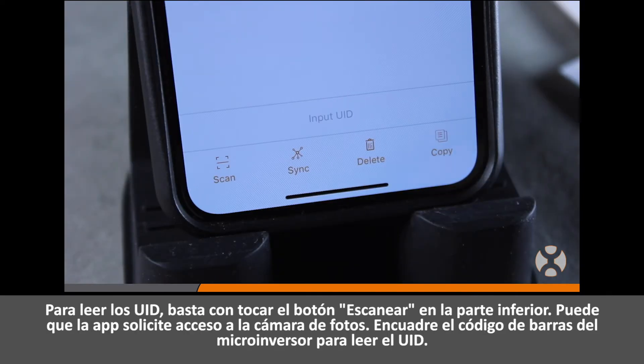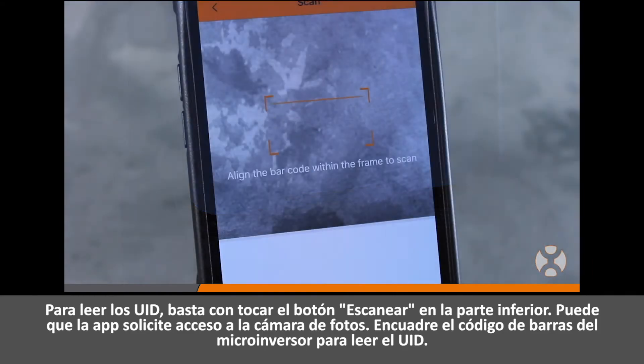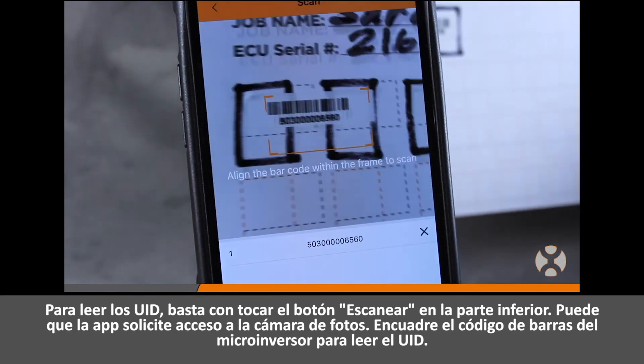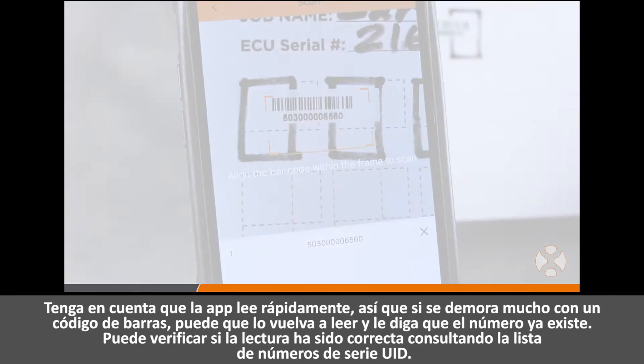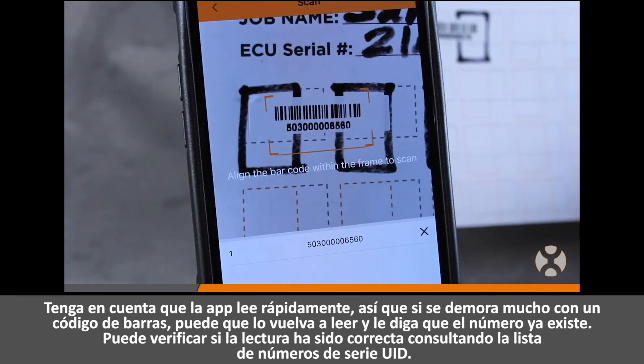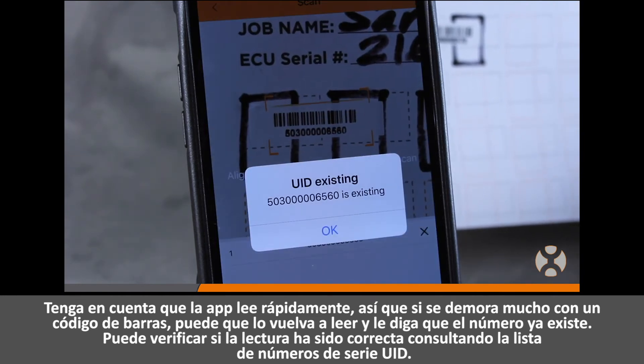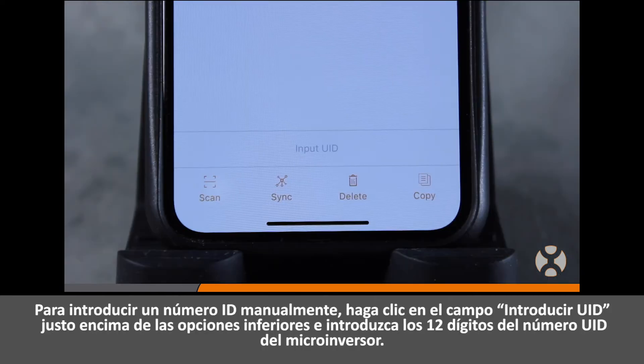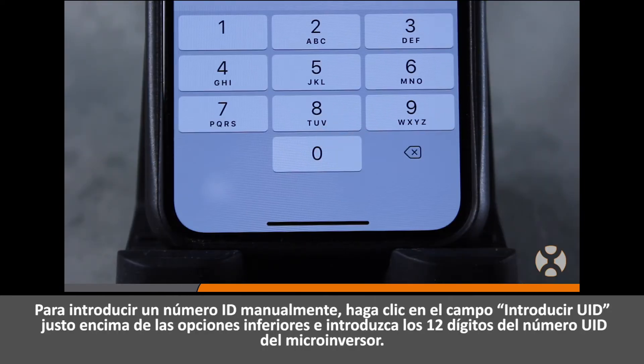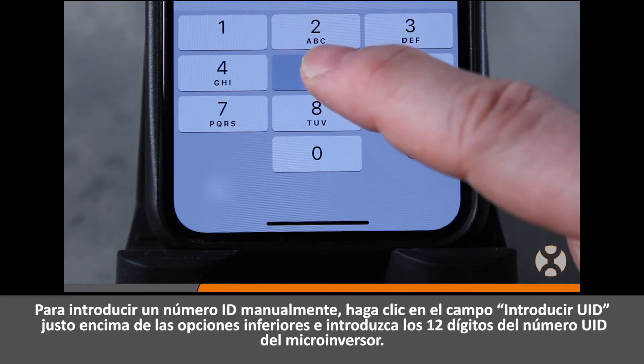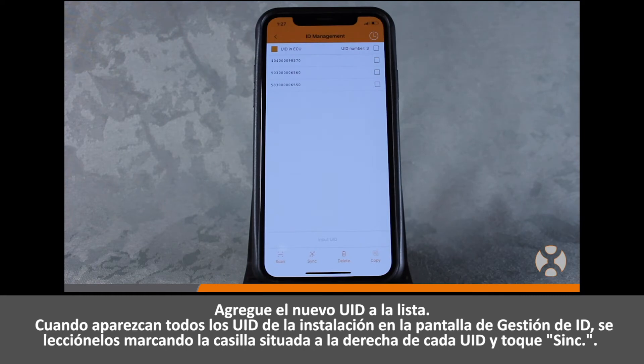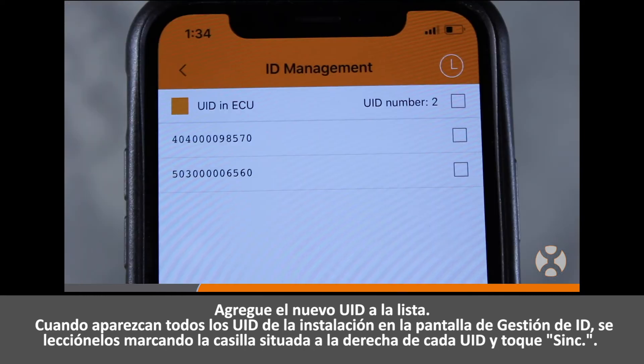To scan the UIDs, simply touch the Scan button at the bottom. The app may request access to your camera — simply align the barcode on the microinverter within the frame to scan the UID. Bear in mind the app scans quickly, so if you linger on a barcode it may scan it again and tell you the number already exists. You can verify a successful scan by looking in the list for the UID serial numbers. To manually enter a UID number, click on the input UID field just above the bottom options and enter the 12-digit microinverter UID number. After all the array UIDs appear on the ID Management screen, select them using the box to the right of each UID and touch Sync.